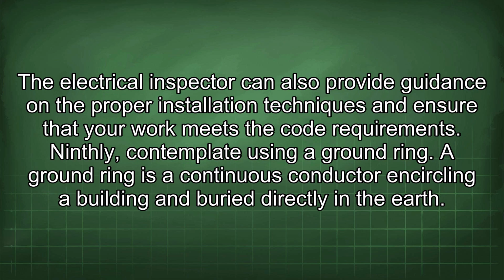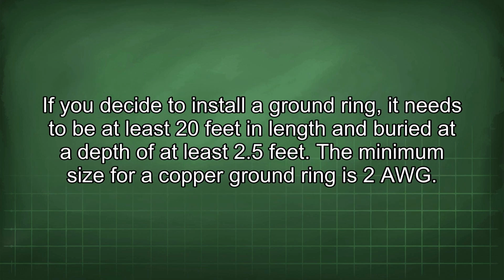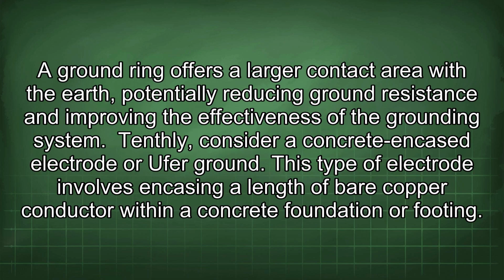Ninthly, contemplate using a ground ring. A ground ring is a continuous conductor encircling a building and buried directly in the earth. If you decide to install a ground ring, it needs to be at least 20 feet in length and buried at a depth of at least 2.5 feet. The minimum size for a copper ground ring is 2 AWG. A ground ring offers a larger contact area with the earth, potentially reducing ground resistance and improving the effectiveness of the grounding system.